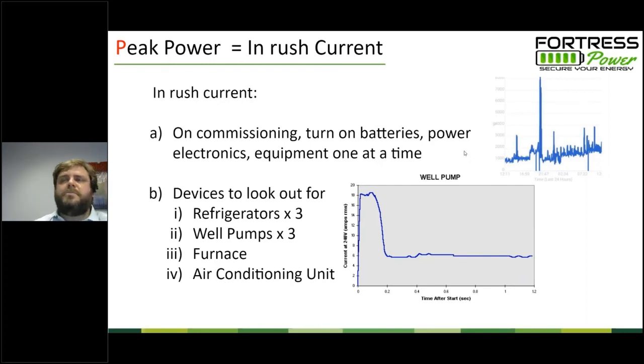And so installing a consumption meter locally, not just relying on, maybe your utility already gives you 15-minute interval data or hourly interval data. Putting a consumption meter inside your electric service panel to know exactly what's going on with your electricity is always a good idea when you're dealing with solar battery systems, because you can see that there are certain loads, namely well pumps, that can spike up rather quickly. And particularly if you're already operating at the top of your inverter capacity and that well pump turns on, that can trigger an error depending on the internal architecture of the units. So often with higher end components, you don't have the same issues as you would if you're using a lower quality battery inverter, for example.